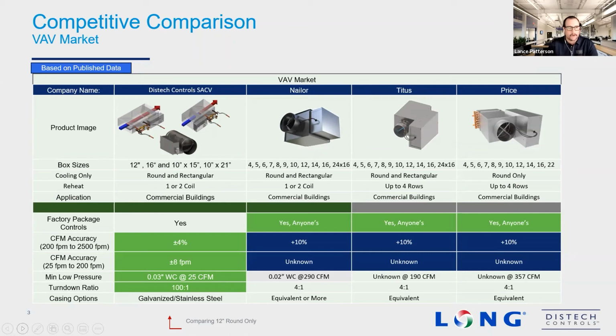If you look at the accuracy between 200 to 2,500 feet per minute, we're plus or minus 4%, which is incredible accuracy. But where we start looking below that, that really tells most of the story, where we can get down to 25 feet per minute and still maintain an accuracy of plus or minus 8 feet per minute. That's pretty low airflow, pretty low velocity. The minimum velocity pressure that we're looking for coming in is 0.03 inches at 25 CFM. We're able to achieve some really amazing turndown ratios. If you look at the 100 to 1 versus 4 to 1, it's incredible. And what all this really tells you is the box size availability.